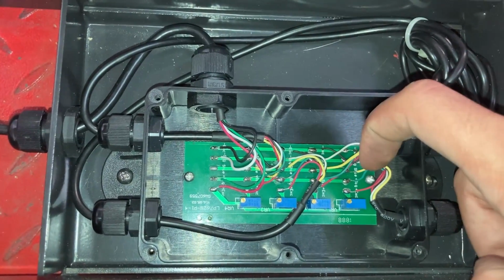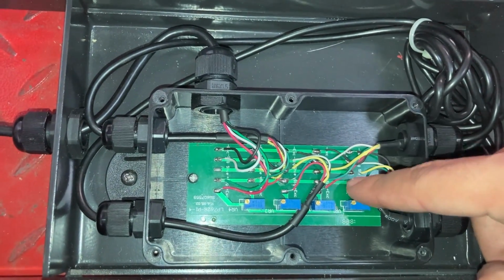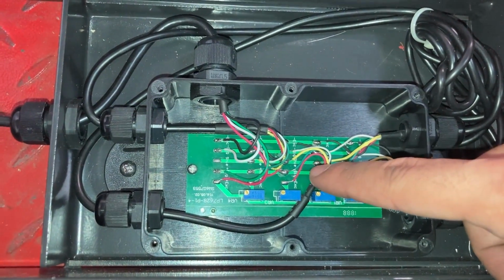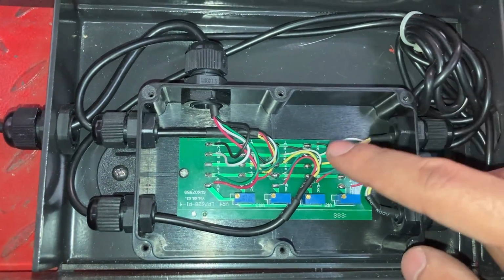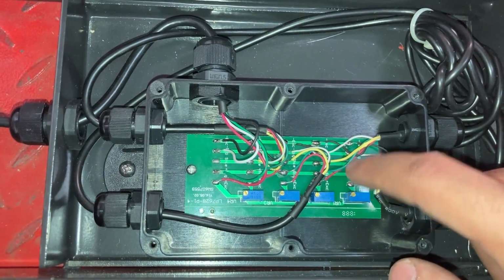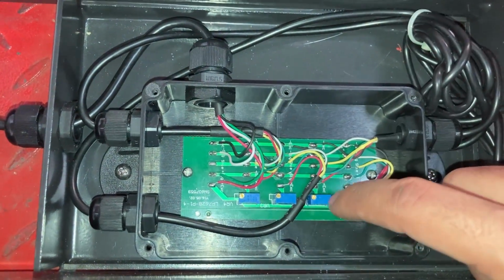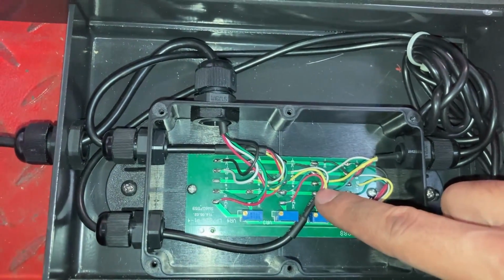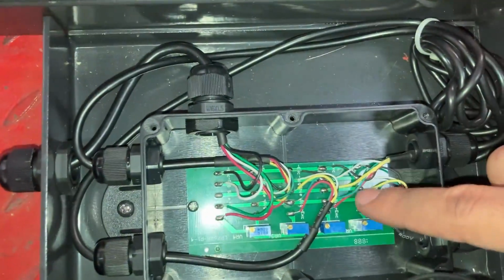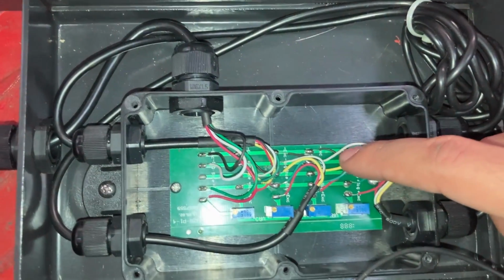So I'd have to unsolder, and then maybe move one of the good load cells from another corner over, and see if that works. If you move it over and the problem is still in the same corner, then the junction box is bad. But if you move it over and the problem moves with it to that corner, then your load cell is bad, and that sensor has to be replaced, which is difficult but theoretically possible.